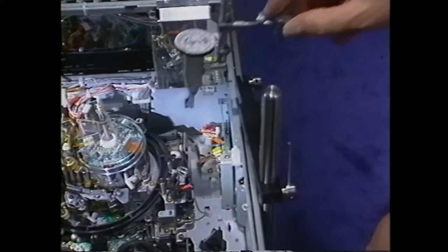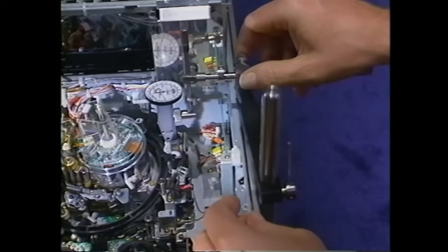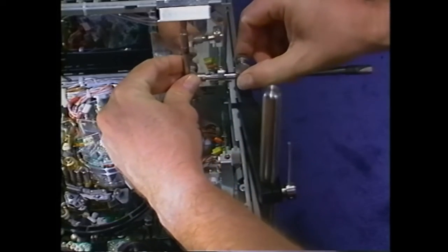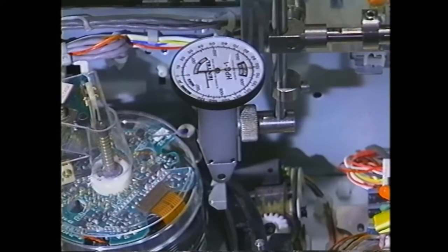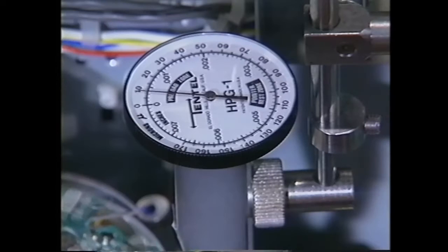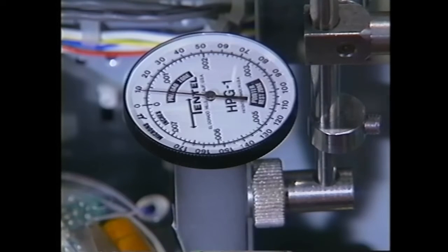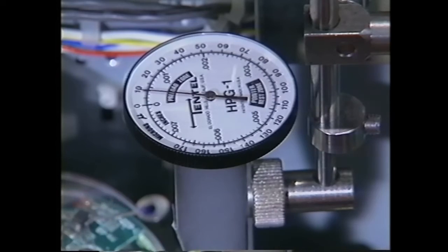The indicator foot can be placed anywhere on the upper drum for drum eccentricity measurements. The X micrometer adjustment is used to bring the indicator into a convenient measuring position on the scale. The total indicated reading as the drum is rotated should be 5 microns or less.